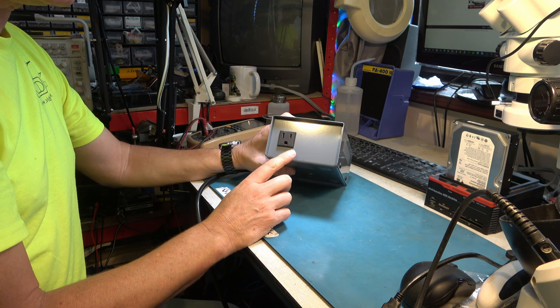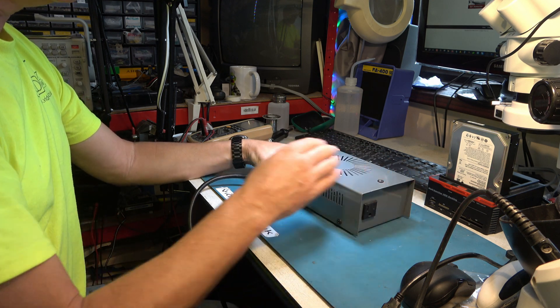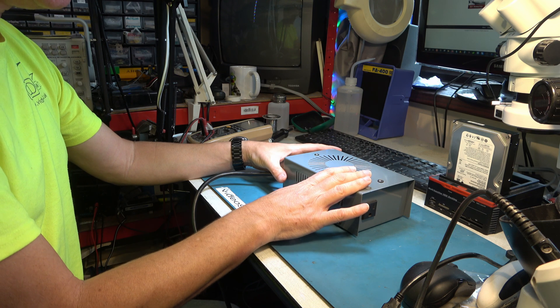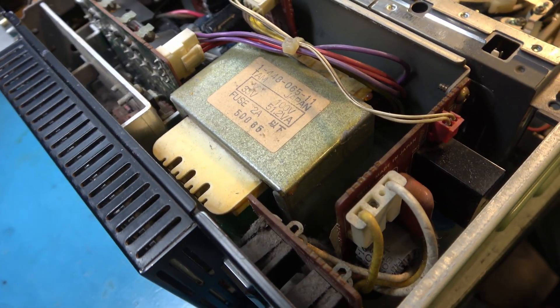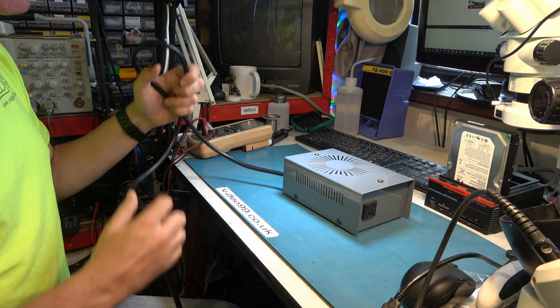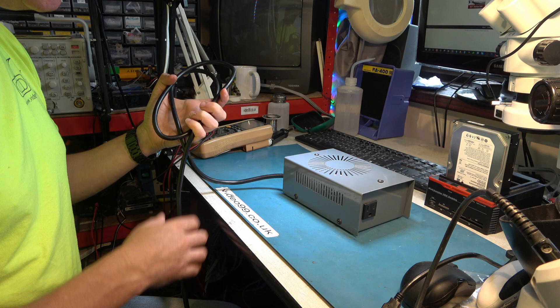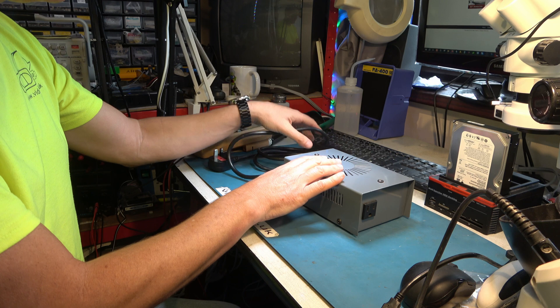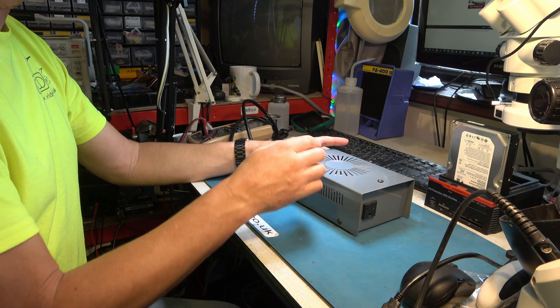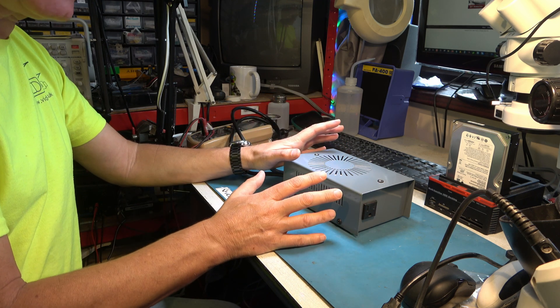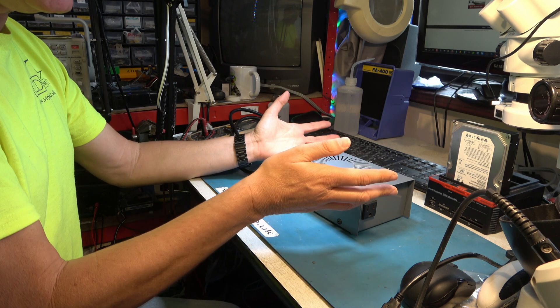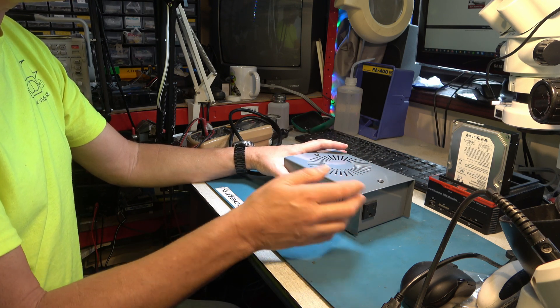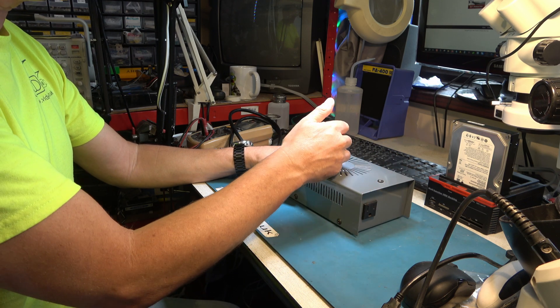Now, under what circumstances may that not be the ideal solution? Well, there is some argument that noise can travel through this more than would happen with an isolation transformer. But remember, we have an isolation transformer in a video recorder, so I'm not too worried about that. But if you had a system that was a chopper supply on the output side, then the noise could be an issue. Also, if there was a failure within the transformer, you could potentially get a situation where a very high voltage was applied to the output. It's extremely unlikely, not really a consideration.